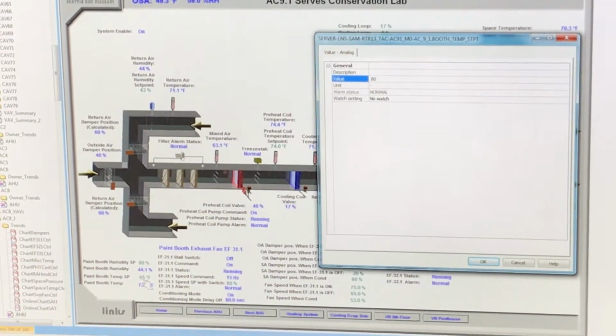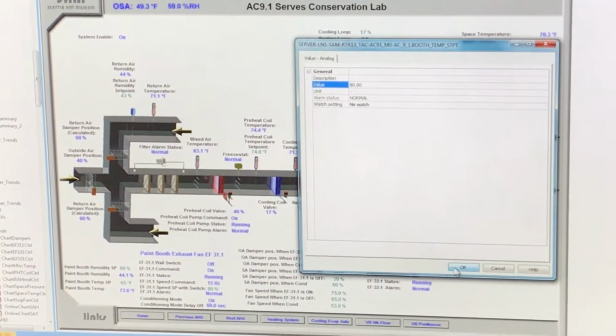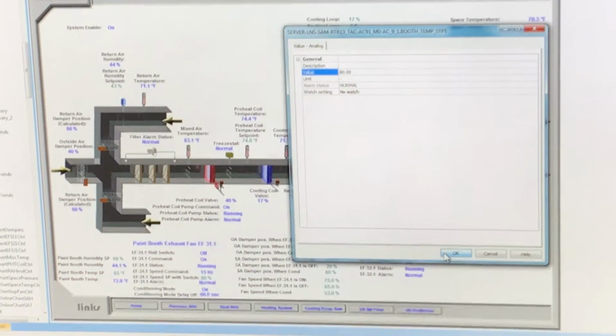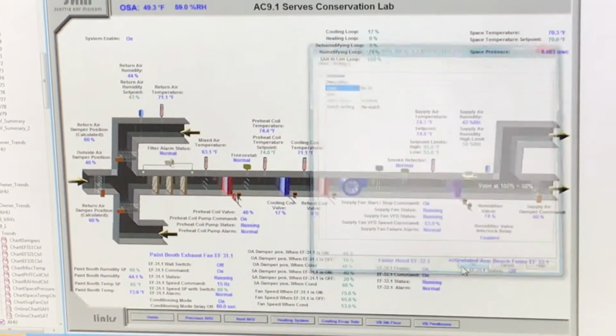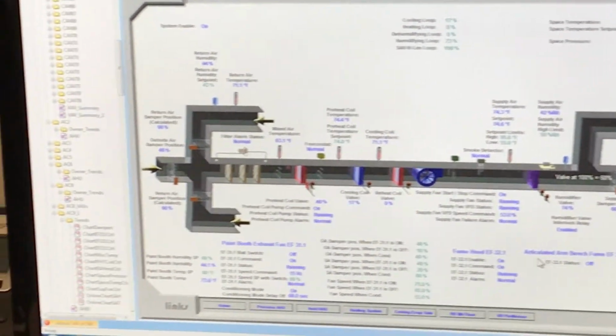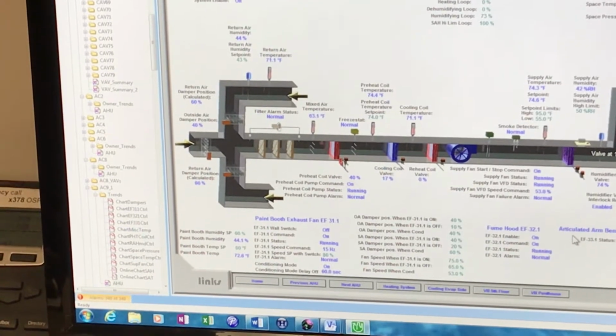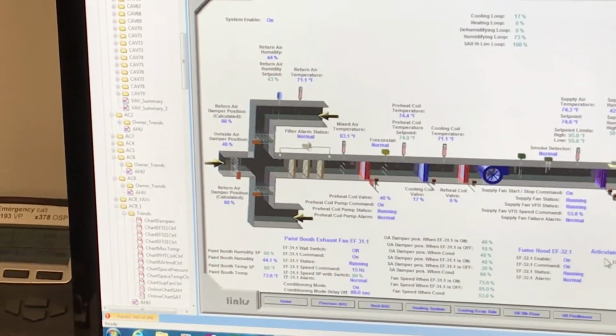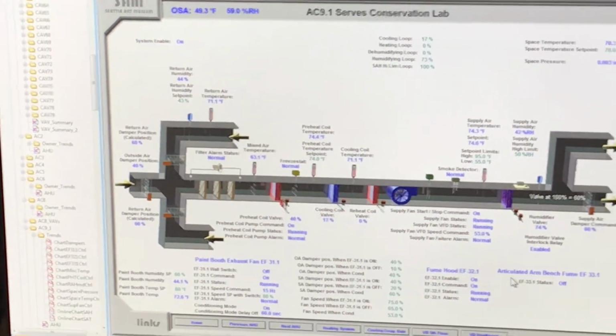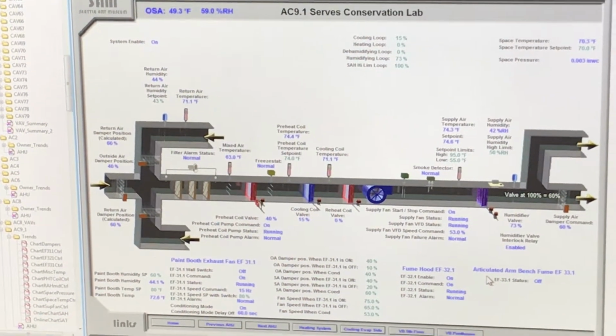It's really the modes: whether you activate the override, the humidity mode, whether you change the humidity set point, or whether you override the fan speed on the exhaust fan. I think those are the values that you can really adjust. All the others, the supply air damper and outside air percentage, are set by the balancing guy.